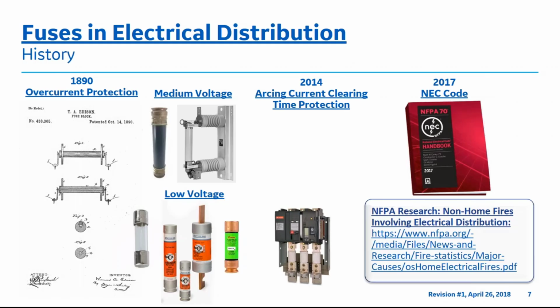The I²T rating is related to the amount of energy let through of the fuse element as it clears the electrical fault. Current limiting fuses have been introduced to operate quickly, where they limit the total let through energy that passes into the circuit, helping to protect downstream equipment from damage. Throughout the course of time, up to 2013, the fuse is safeguarded from bolted faults.